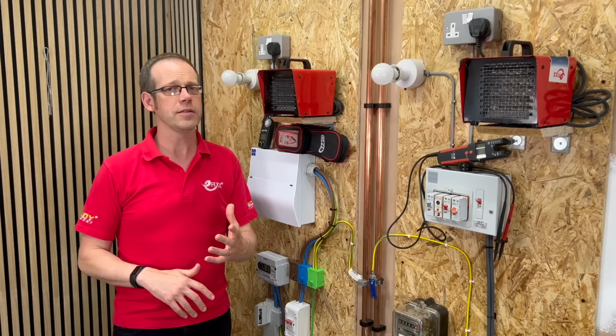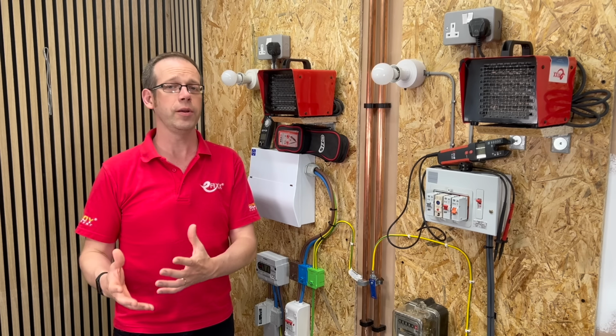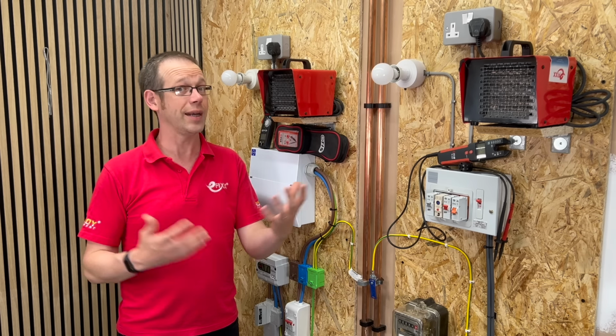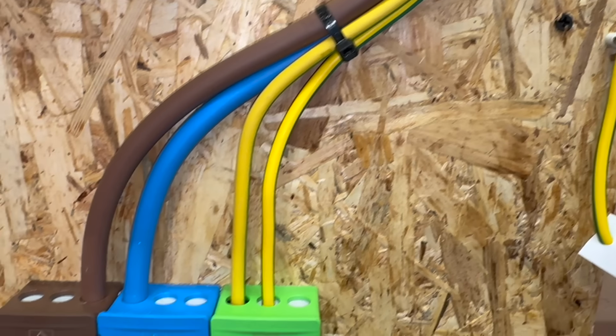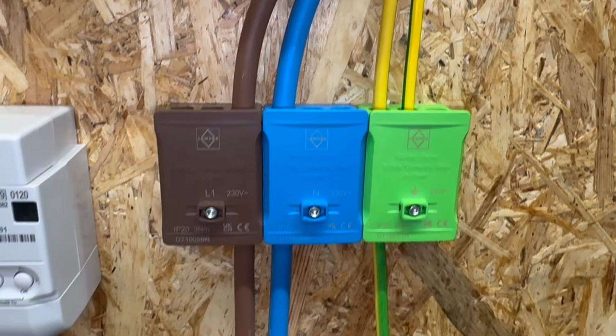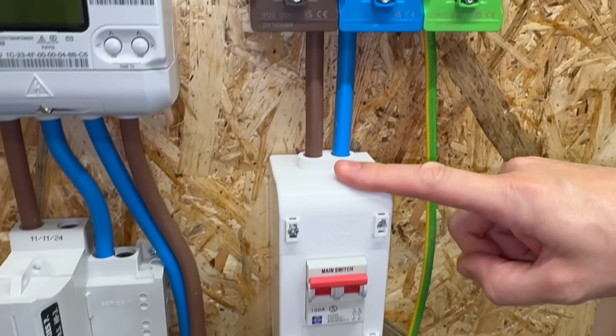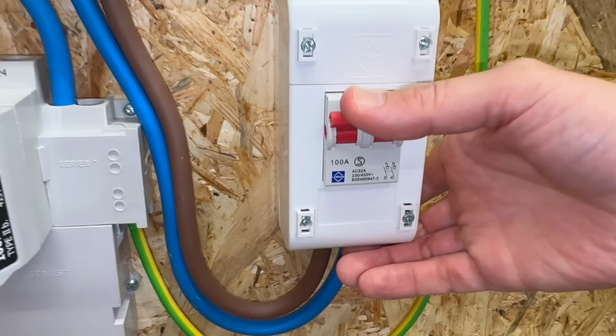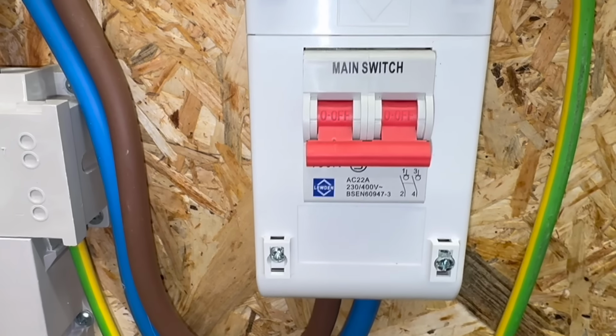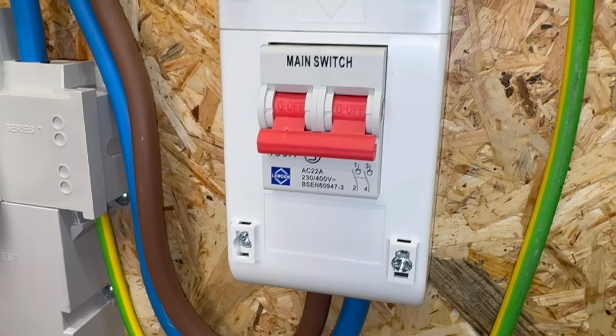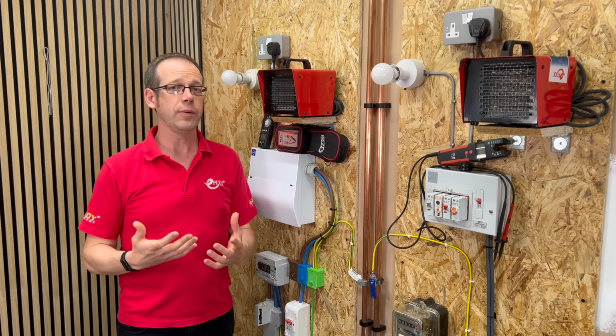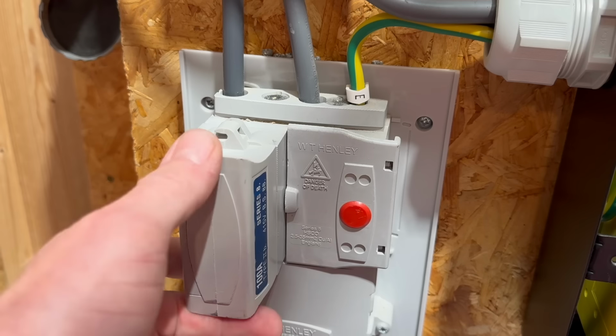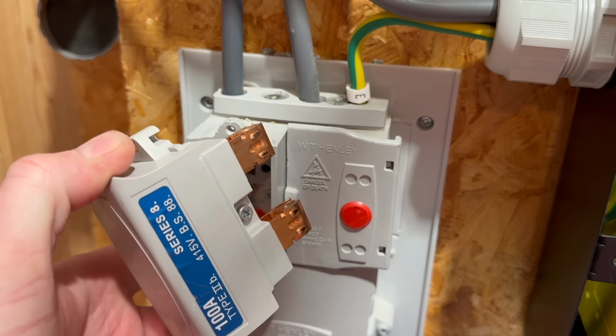When undertaking certain types of work, such as replacing a consumer unit or installing an additional one for an EV charger, you may need to isolate the meter tails, that's the cables running from the electricity meter into the consumer unit. If you're lucky, a double pole isolator may already be installed. This is common in newer properties and allows for a safe, convenient disconnection of the supply. However, if no isolator is present, the only way to isolate the supply is by removing the service fuse, which requires breaking the supplier's seal.